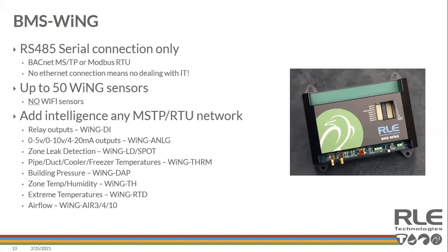The greatest story is my colleague sold some of these BMS wings to a high-rise recently, and they deployed wireless leak detection and spot detection. They got a leak at about 4 in the morning, and the integrator was smart enough, since it was in the penthouse, to integrate a water valve to shut off. So when they got the alarm, they didn't have nine floors of damage to remedy.